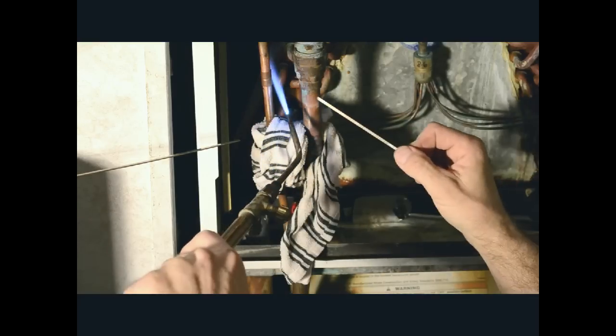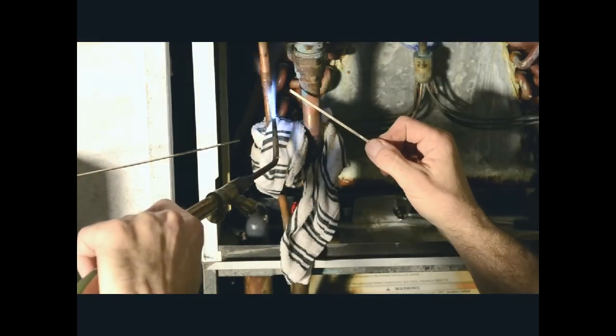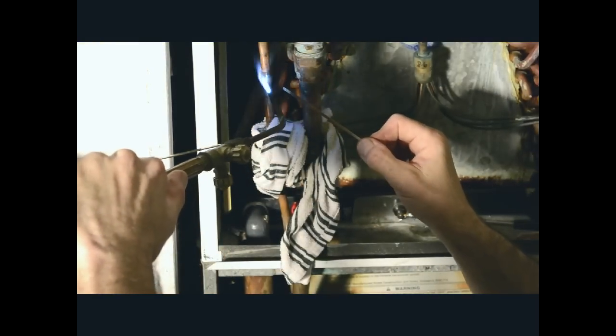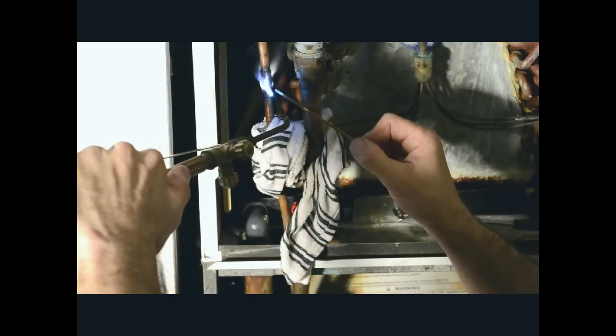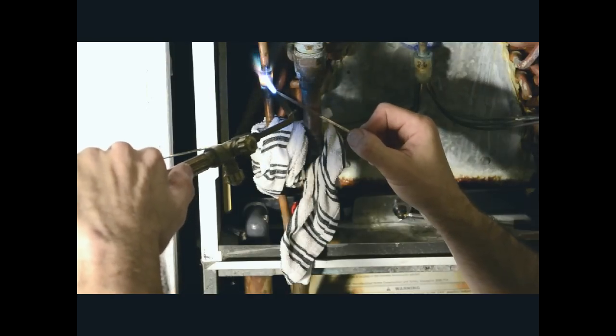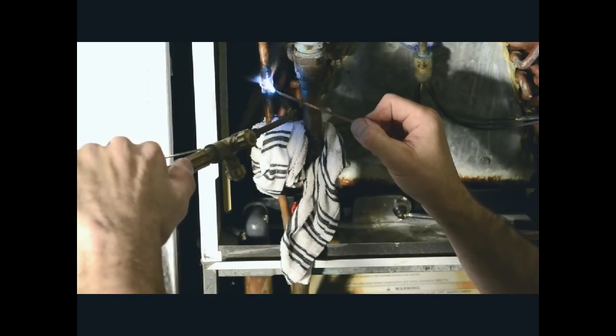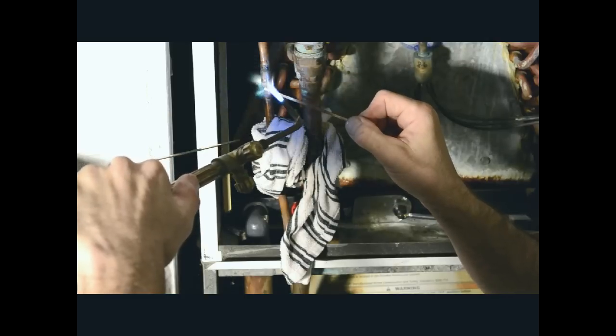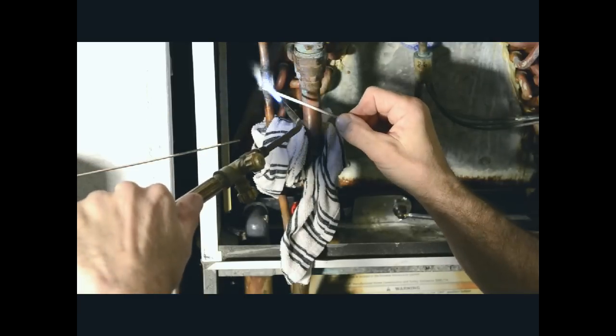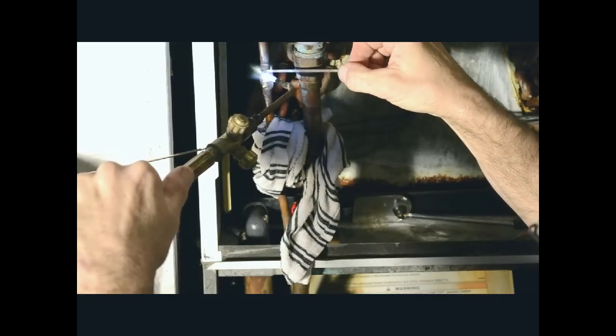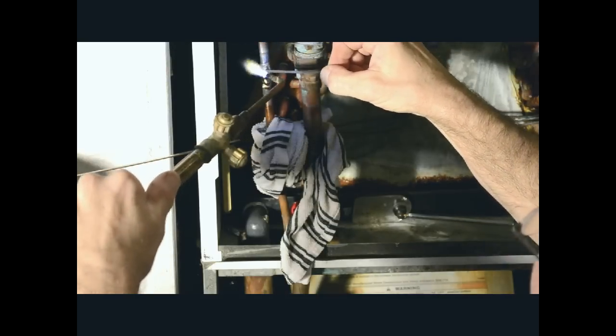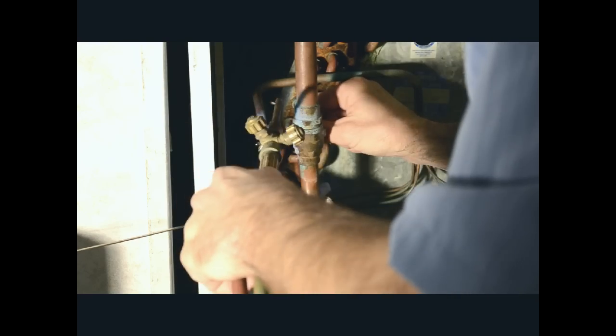I've heard stories of people trying to do their own welding on HVAC stuff and use plumber solder and it blows right out. The small ones heat up a lot easier and quicker. These are a lot easier to do as far as filling these in. One thing you have to be careful with these is not to get them too hot, cause then they drip. And if you get it too hot you can actually melt a hole in it real quick. Let's see if we're lucky we'll get that in one pass.